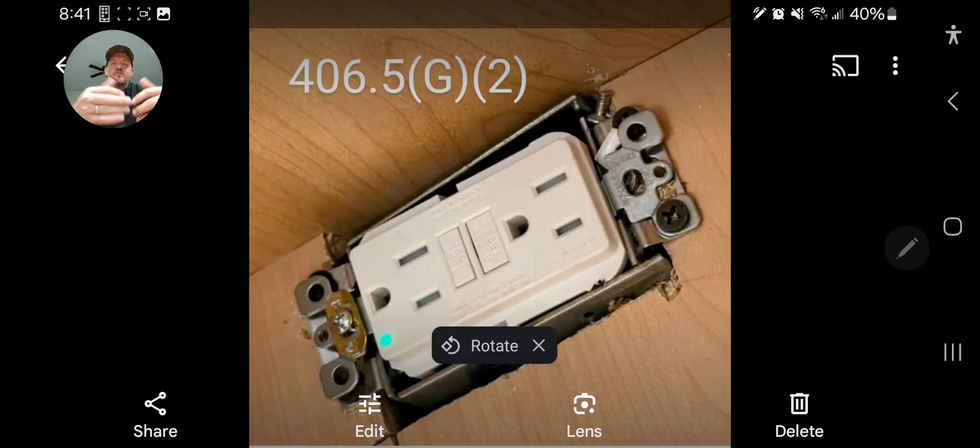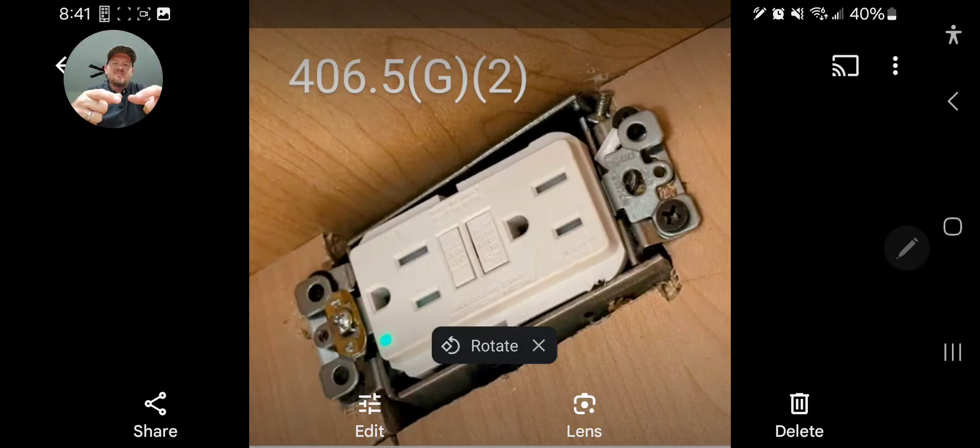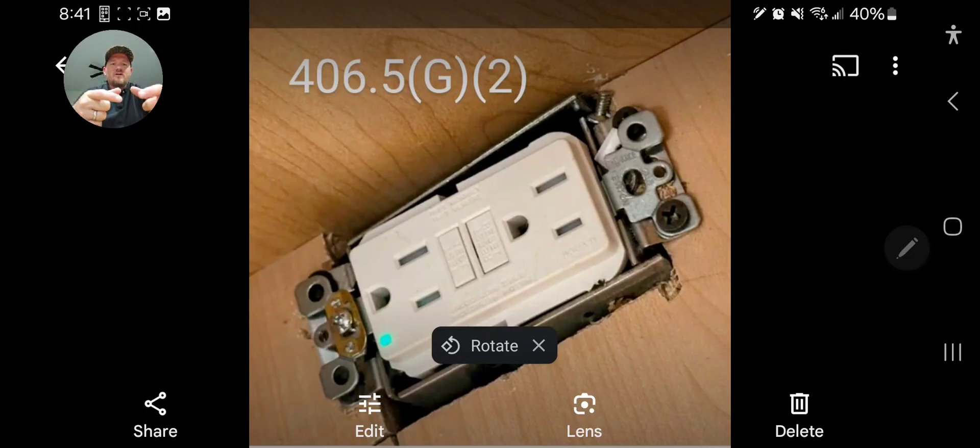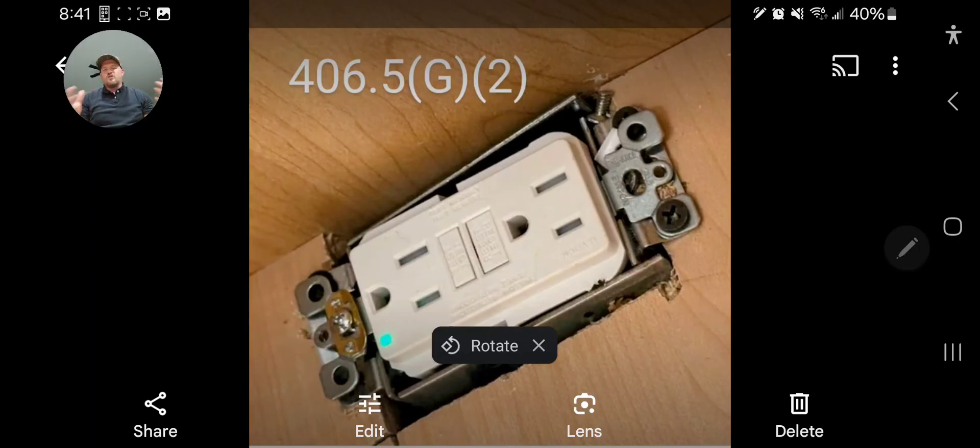Underneath the sink if you're doing your garbage disposal or if you're doing your dishwasher, you are no longer allowed to, I think it's 2017 and later, you are no longer allowed to install those receptacles in the face-up position underneath a sink.